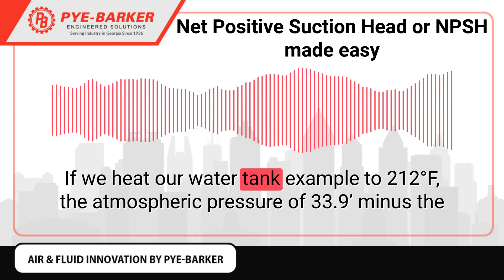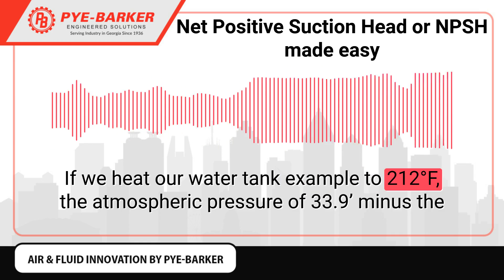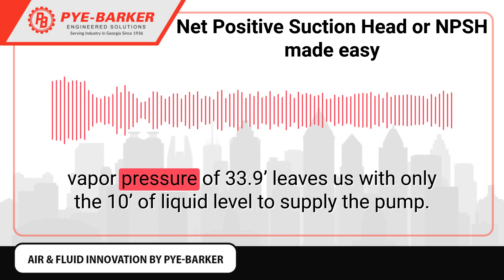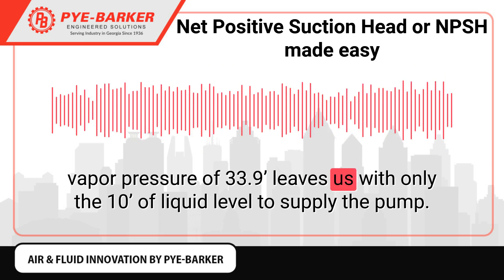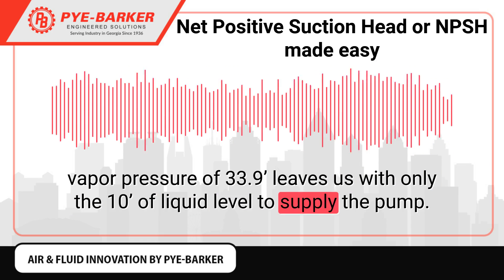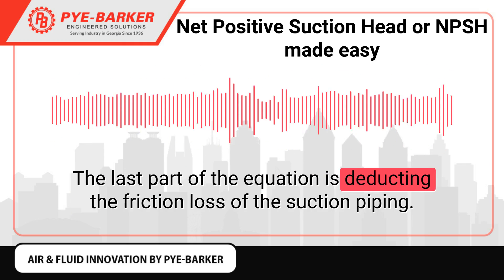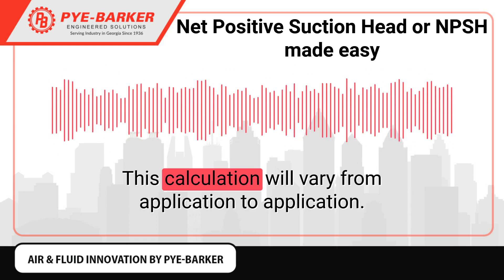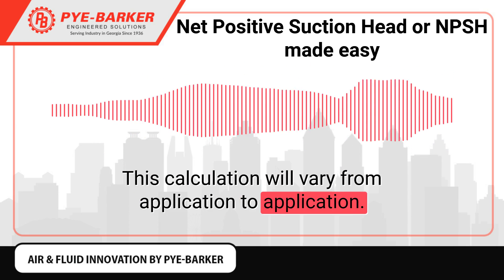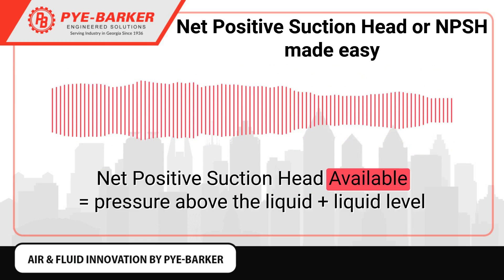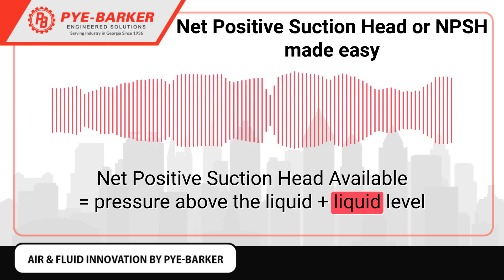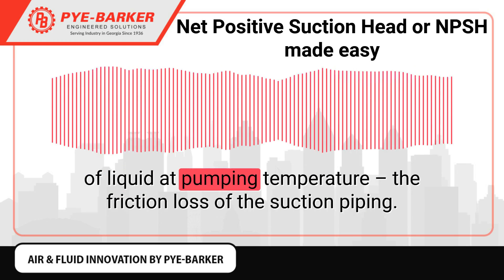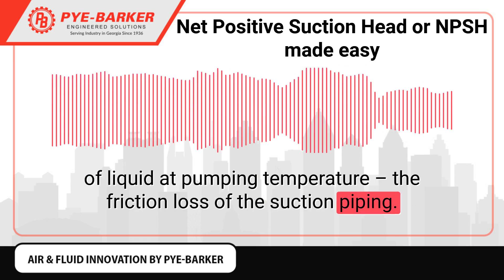If we heat our water tank example to 212°F, the atmospheric pressure of 33.9 minus the vapor pressure of 33.9 leaves us with only the 10 feet of liquid level to supply the pump. The last part of the equation is deducting the friction loss of the suction piping. This calculation will vary from application to application. Net Positive Suction Head Available equals pressure above the liquid, plus liquid level above the pump, minus the vapor pressure of the liquid at pumping temperature, minus the friction loss of the suction piping.